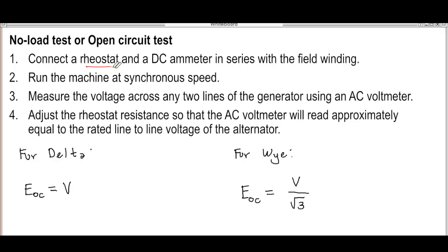So we need to connect a rheostat and a DC ammeter, run the machine at its rated speed, then measure across the two lines, no? Tapos i-adjust mo yung rheostat hanggang sa equal na yung rated line-to-line voltage ng alternator. So yung reading ng voltmeter equal na sa line-to-line voltage ng generator. Okay? So for Delta, equal lang po yung ating open circuit voltage, so yan yung equal na nakukuha na measurement ng voltmeter. For Y, meron siyang i-divide mo siya ng square root of 3.